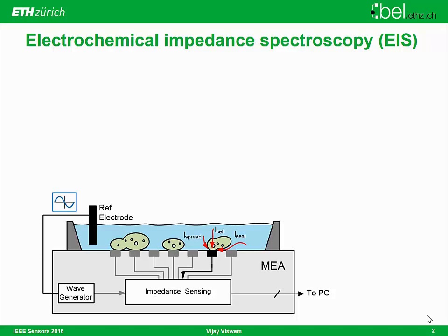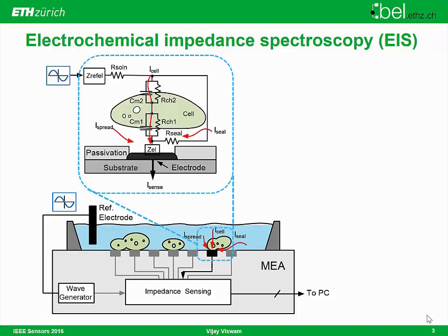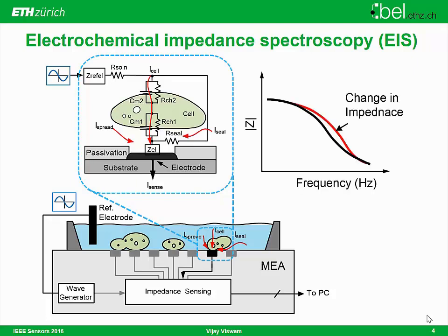This can be modeled using resistors and capacitors in series — representing the electrolyte, the cell, and the electrode interface. The change in this impedance when a cell is sitting on top of the electrode depends on the position, the size, or the attachment of the cell, which you can observe in the impedance spectrum.